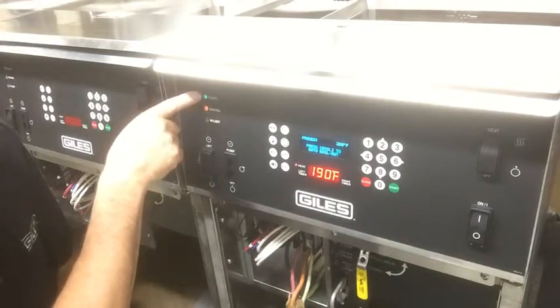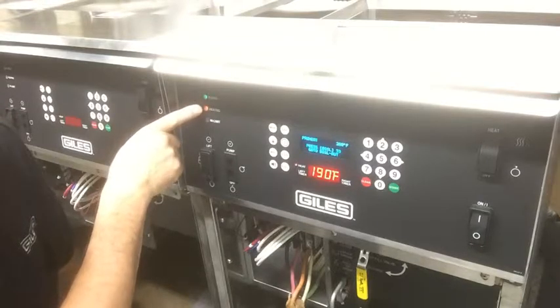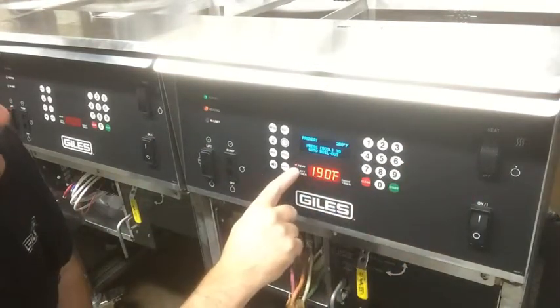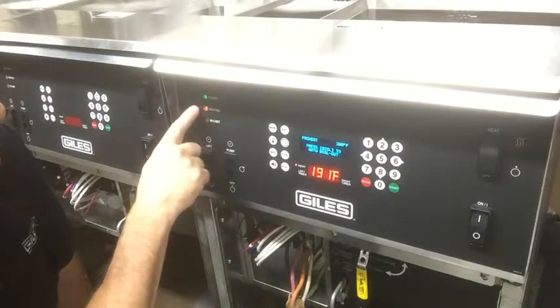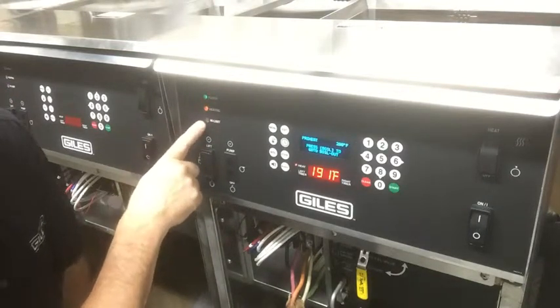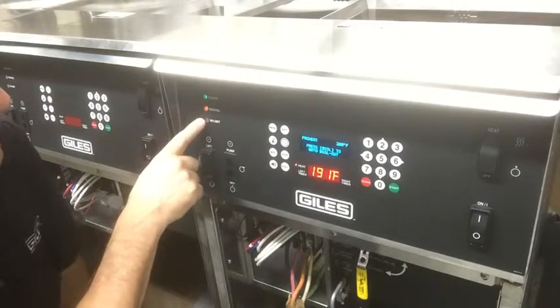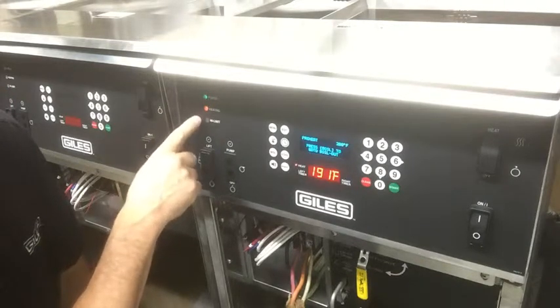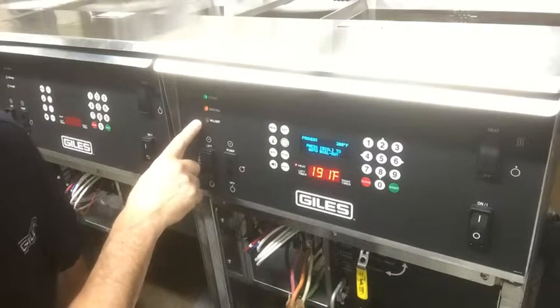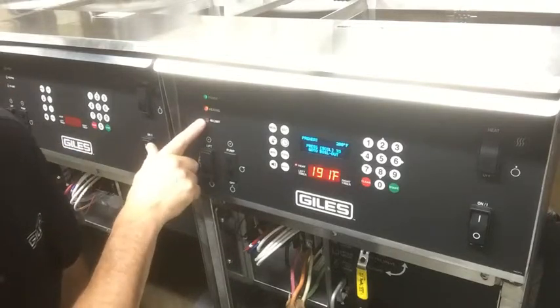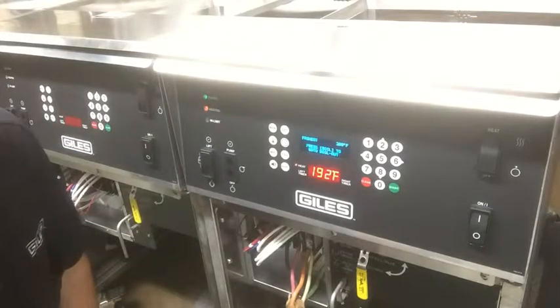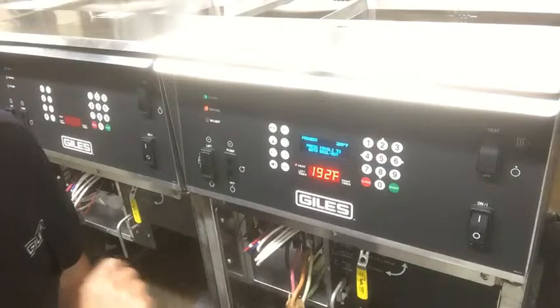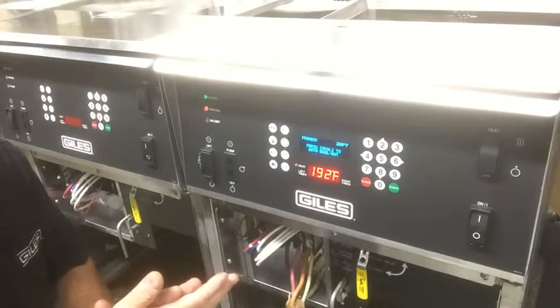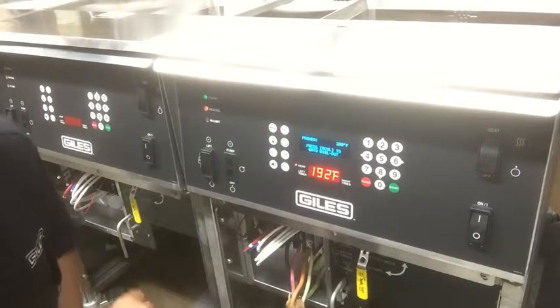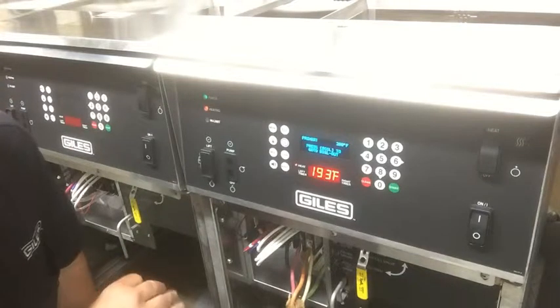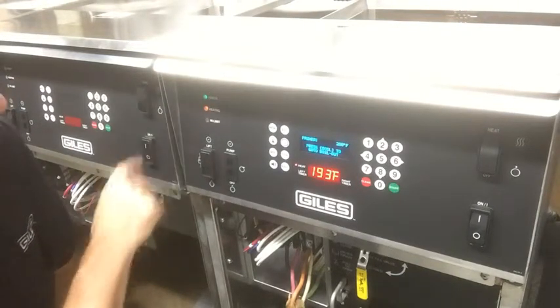While we're doing that, we have the power light on. Our heat light is now on because we have the heat switch on and it's calling for heat. So you've got this orange light on. If this high limit comes on, it's because the sensor has sent a signal to that high limit board that it's over 450 degrees. This would only happen in the case of a runaway temperature, or if that probe sometimes can get bent where it's right up against the heat element. If it's touching that heat element, the heat element will get over 450 degrees pretty quick. So that would do that.